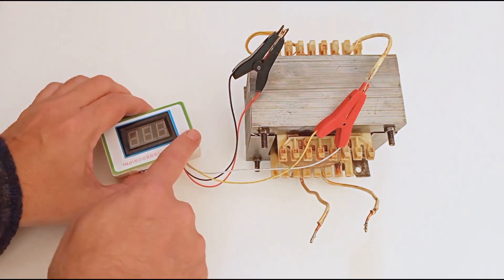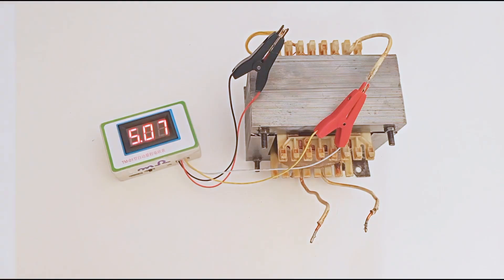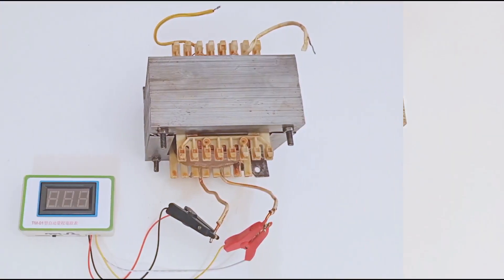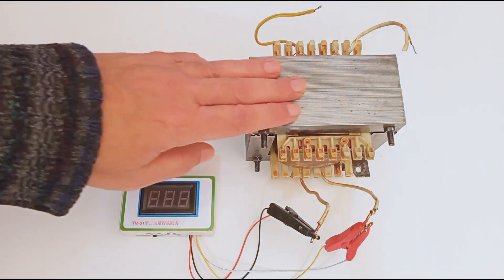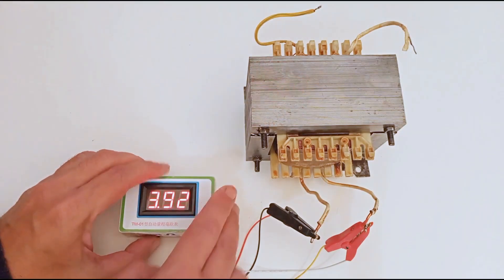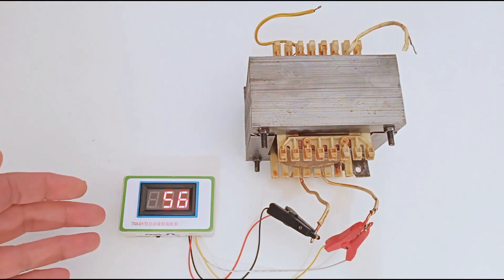It is much better to use a precision bridge milliohmmeter, which eliminates errors caused by measurement cables. Now the measurements are much more precise and reliable, as can also be seen in the final report.